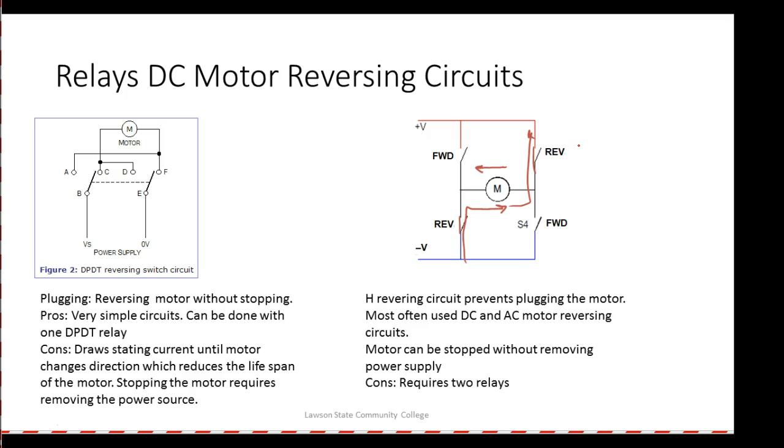Notice that every one of them requires two relays, right? Do y'all understand that? Every one of our lines over here on the armature line that has the ability to reverse has two relays out there.